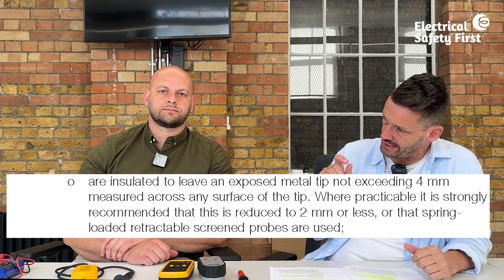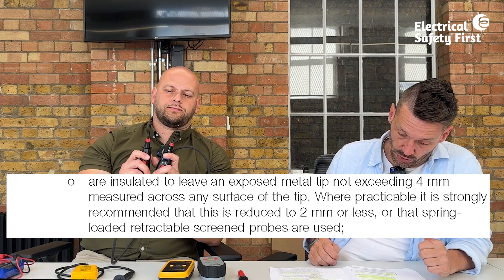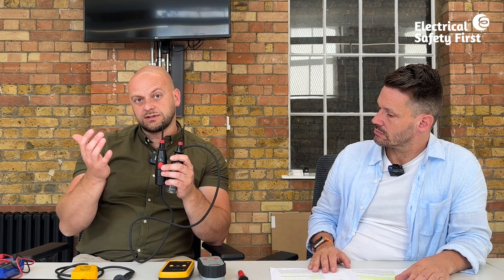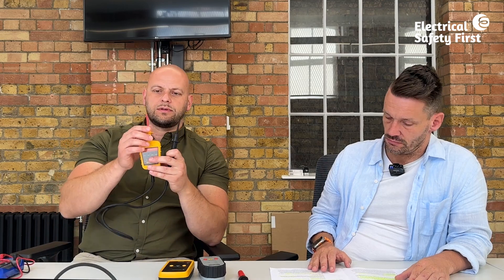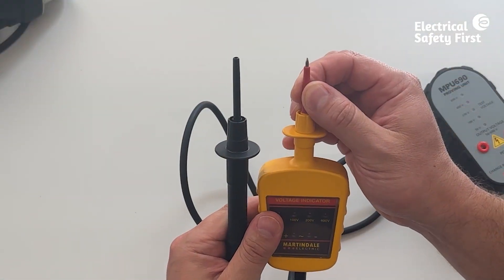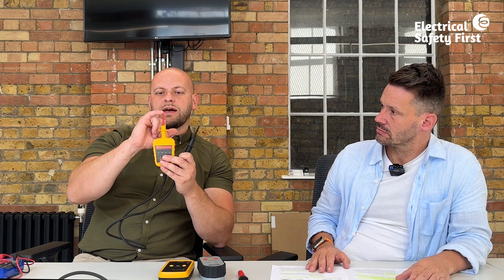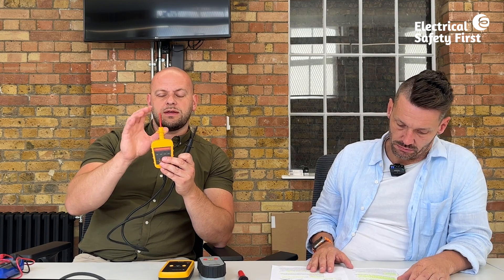GS38 states that probes should be insulated to leave an exposed metal tip not exceeding four millimetres across any surface. Where practicable, it's strongly recommended this is reduced to two millimetres or less, or a spring-loaded retractable type is used. This Martindale tester has four millimetres exposed. The multifunction tester has a spring-loaded retractable tip — hidden until pushed down — which is a real safety feature. No more than four millimetres of metal should be exposed when testing.